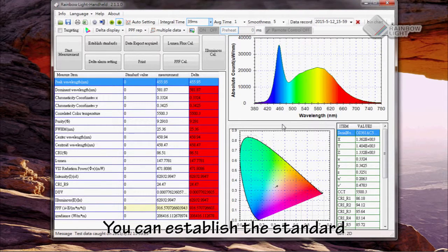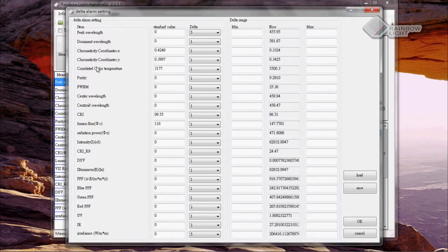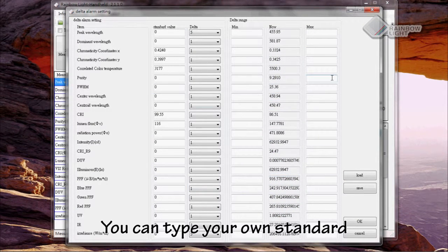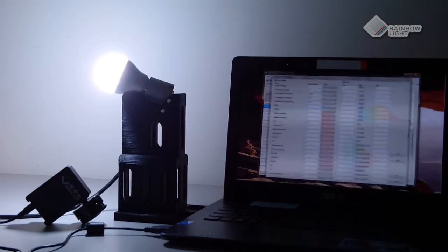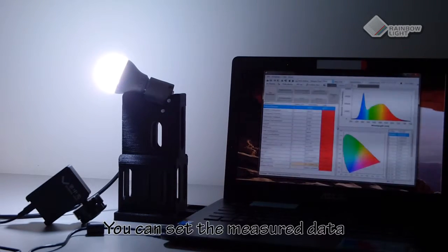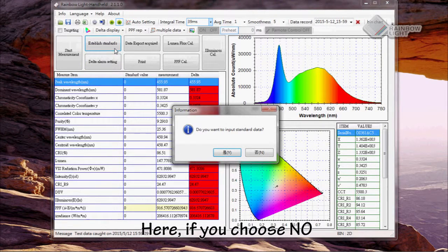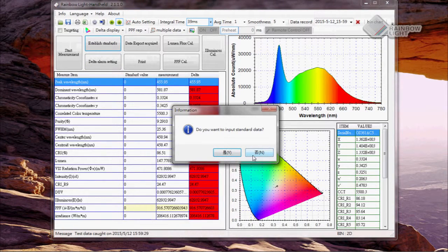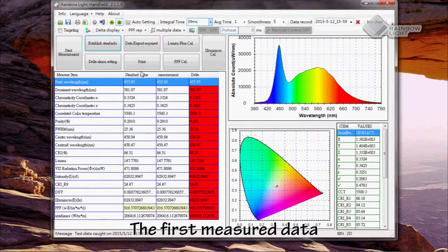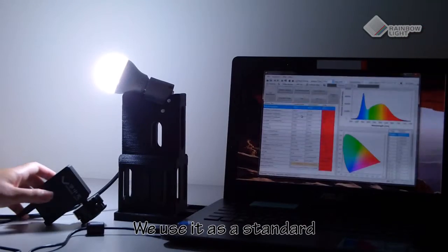You can establish a standard through our delta alarm setting function. Here you can type your own standard. If you don't have your own standard, you can set the measured data as a standard. If you choose no, the first measured data will be moved to the standard value. Right now we are using it as a standard.